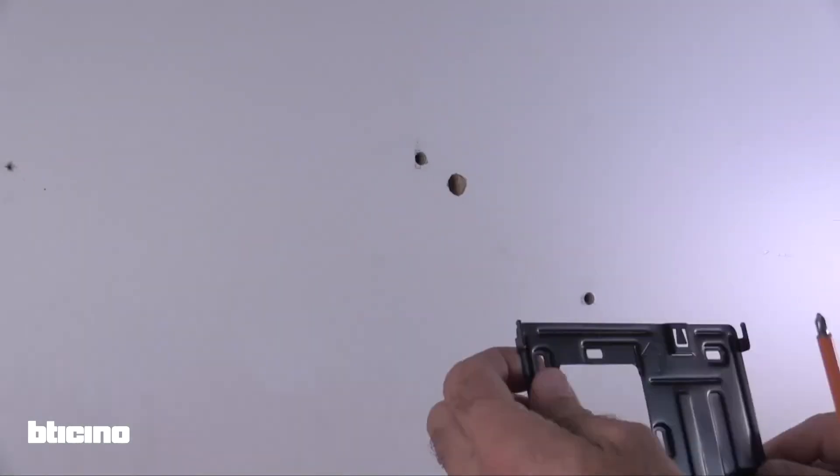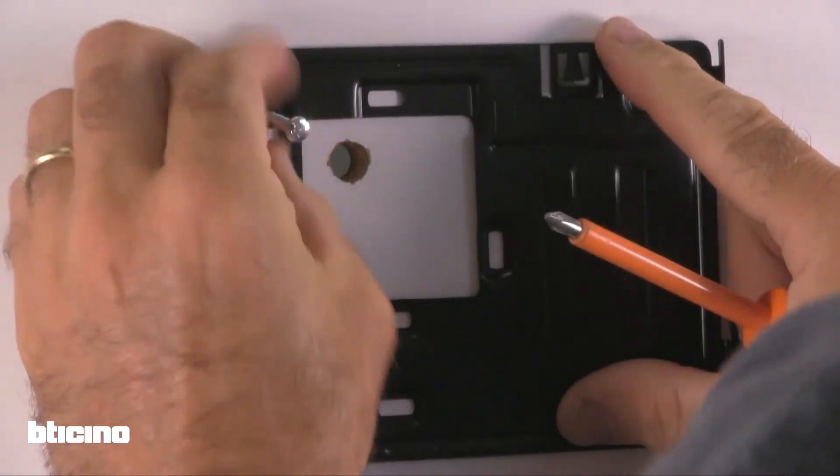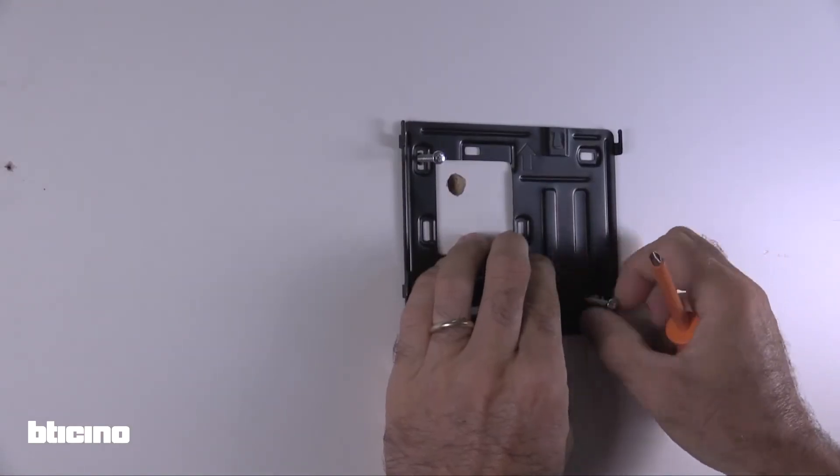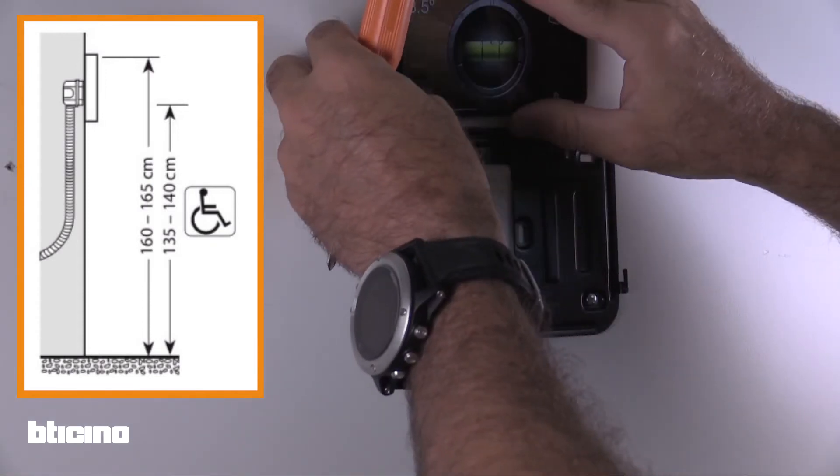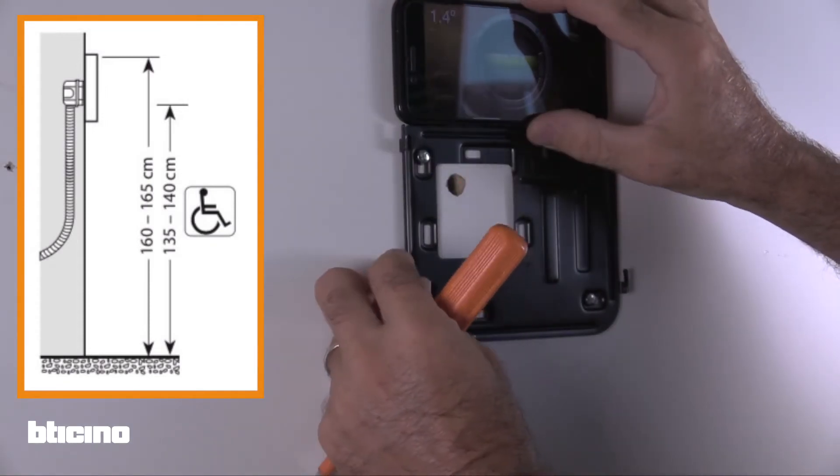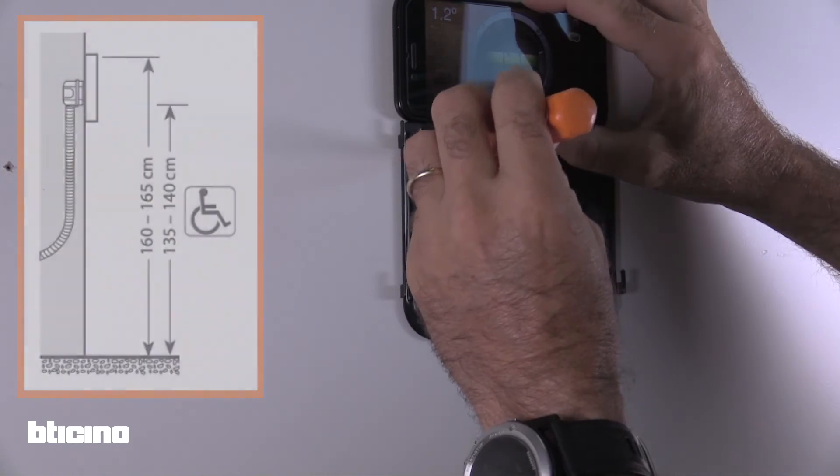Now, let's mount the internal unit. First, fix the metal bracket to the wall. Mount the unit approximately 160cm from the ground and using a spirit level, ensure that it's straight.